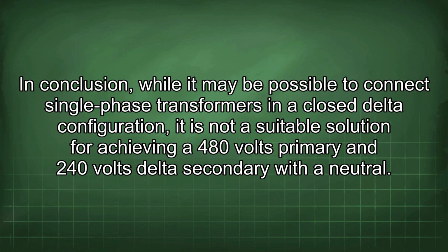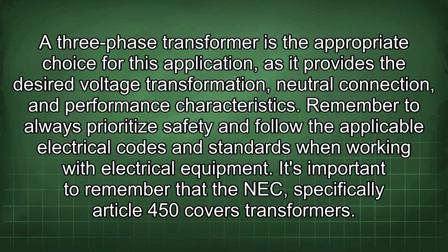In conclusion, while it may be possible to connect single-phase transformers in a closed delta configuration, it is not a suitable solution for achieving a 480 volts primary and 240 volts delta secondary with the neutral. A three-phase transformer is the appropriate choice for this application, as it provides the desired voltage transformation, neutral connection, and performance characteristics. Remember to always prioritize safety and follow the applicable electrical codes and standards when working with electrical equipment.